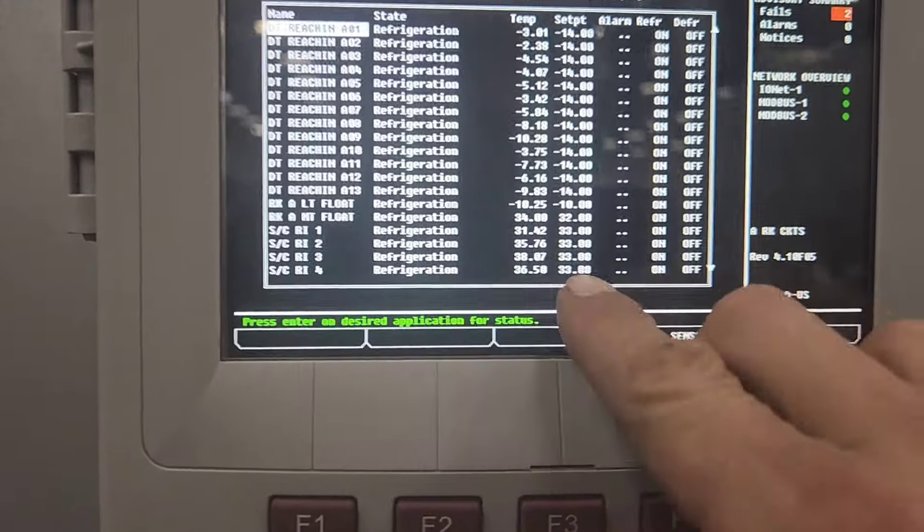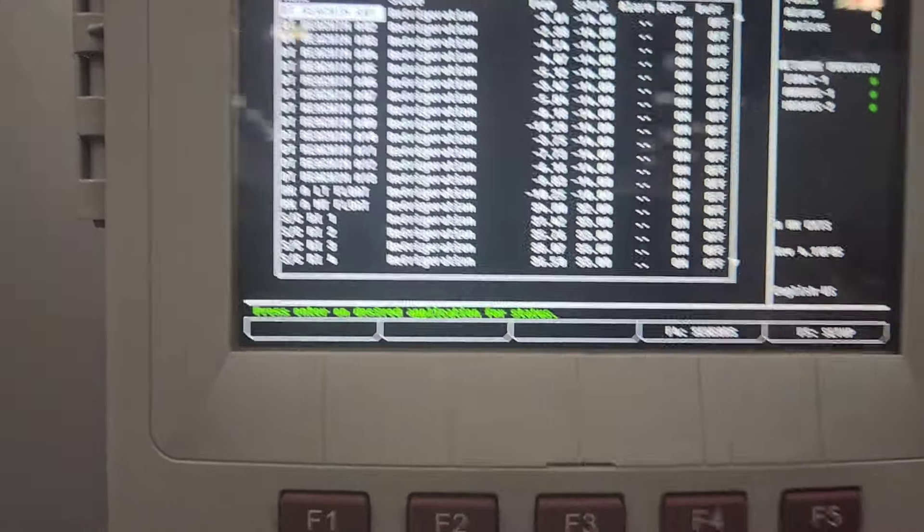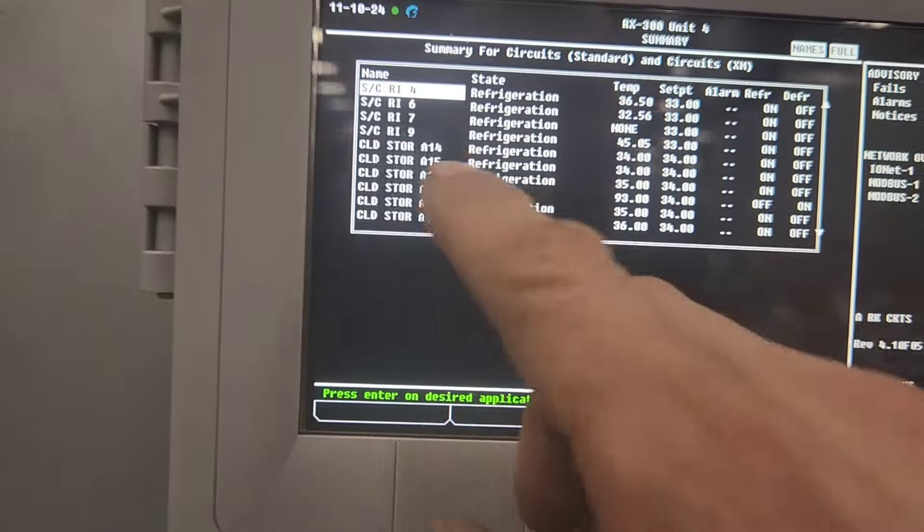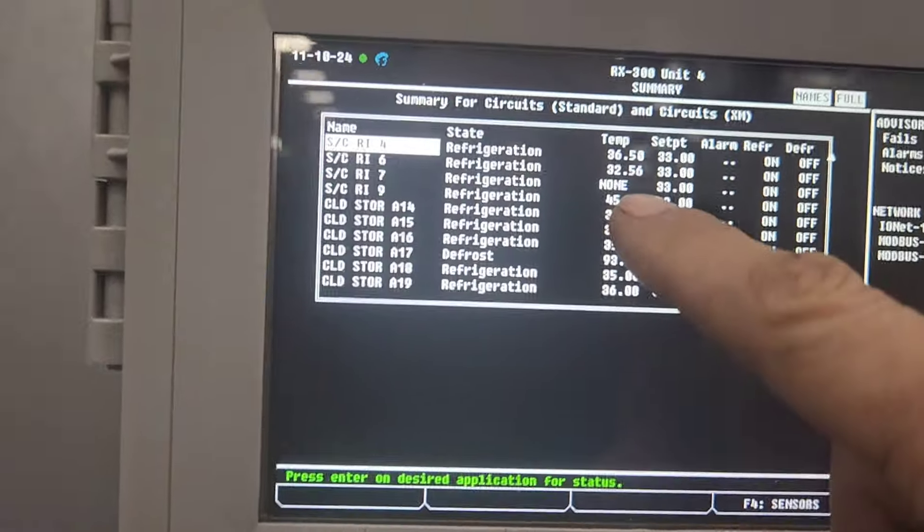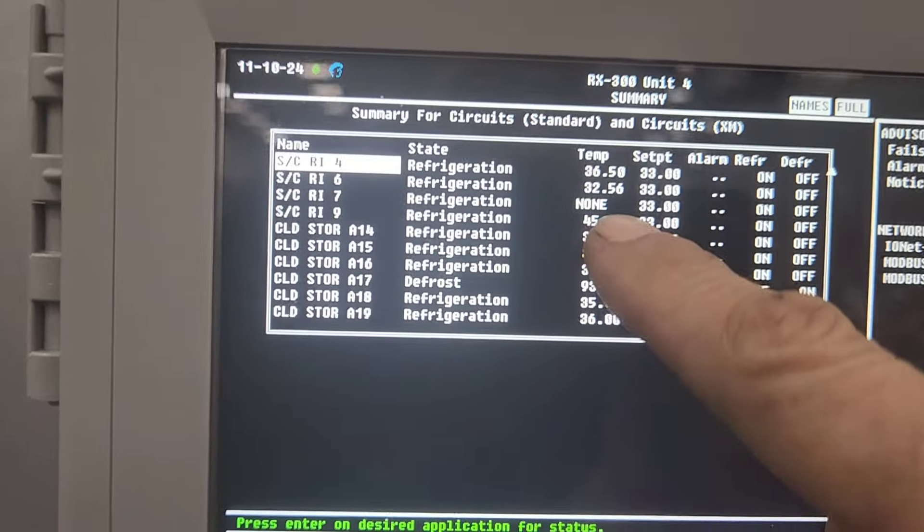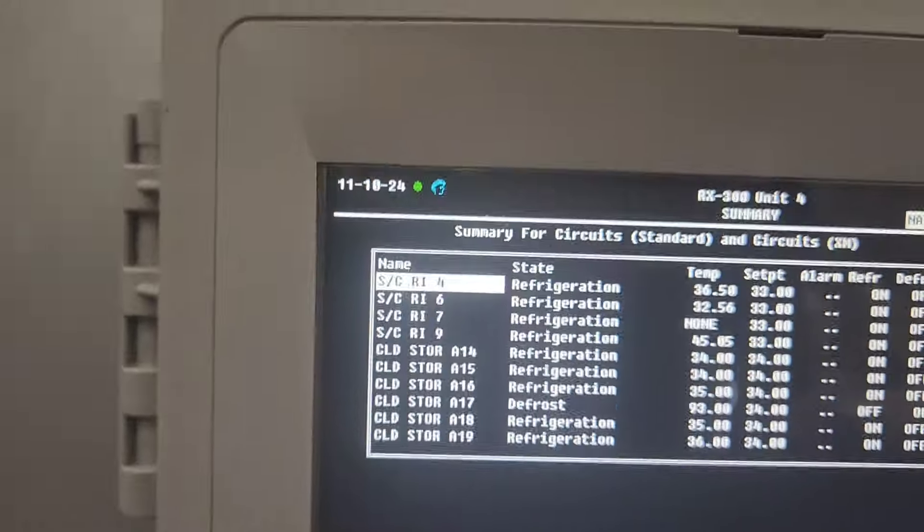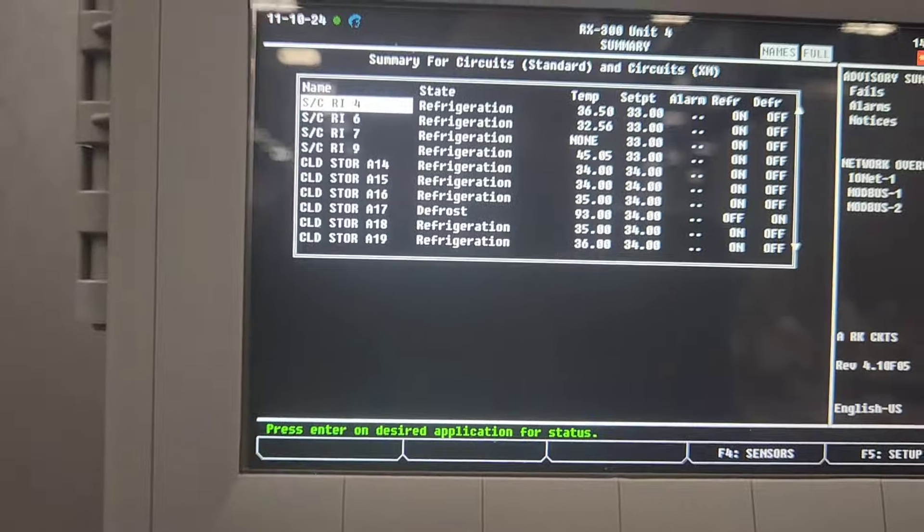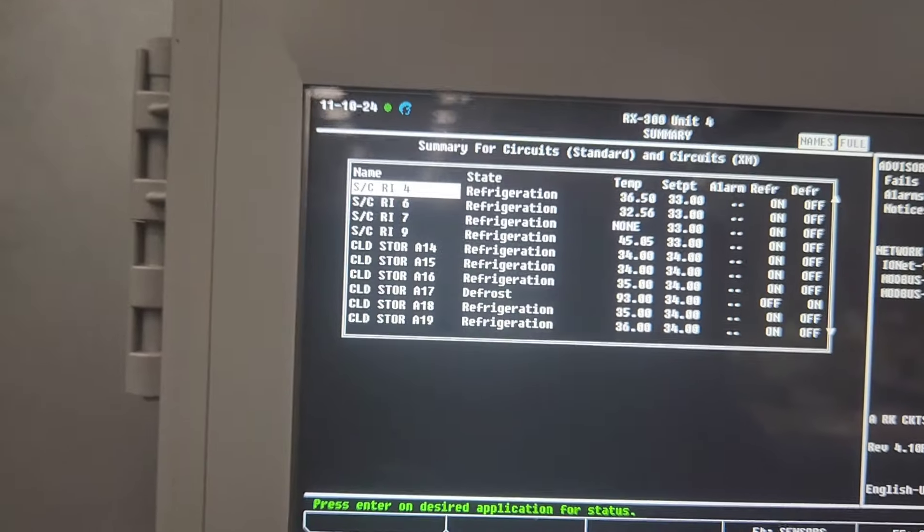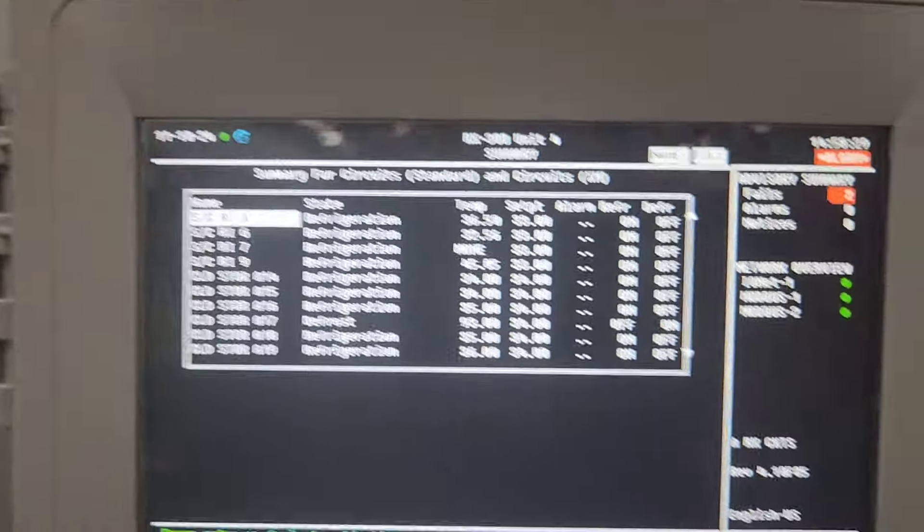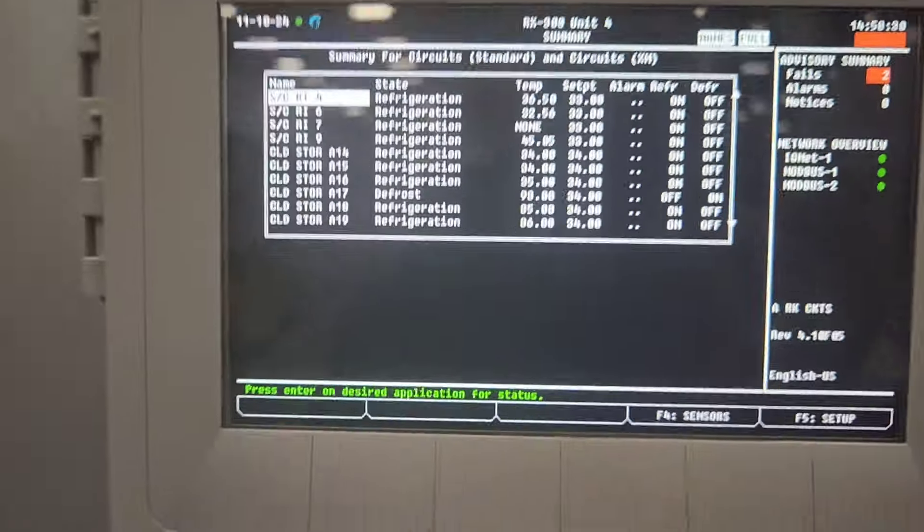All right, so number four is back, no more alarm on that. And then we've got number seven that's not reading, which is fine because number seven module is down. Number seven case is down, it's unplugged and over there in the corner. So we're good.